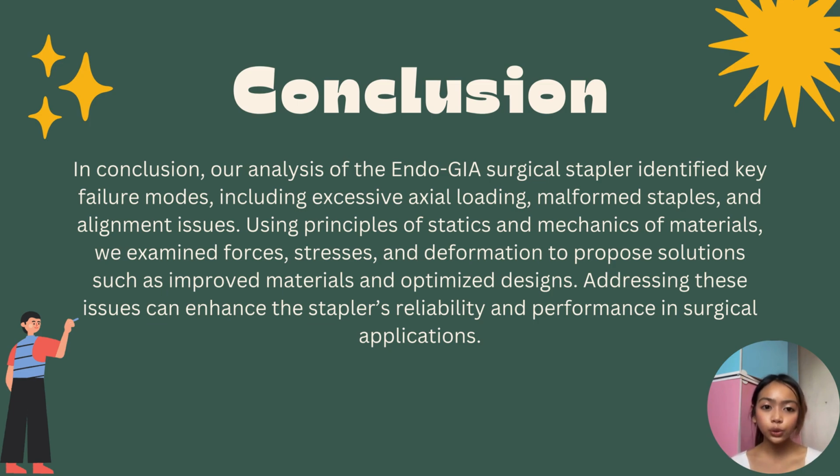We also conducted stress and deformation analysis to understand the stapler's limitations. From this, we propose solutions including material improvements, better alignment mechanism, and optimized designs. Our findings support the hypothesis that load distribution, alignment, and material weaknesses are primary contributors to failure. Addressing these challenges is crucial for enhancing the stapler's reliability and performance, ultimately improving patient outcomes.